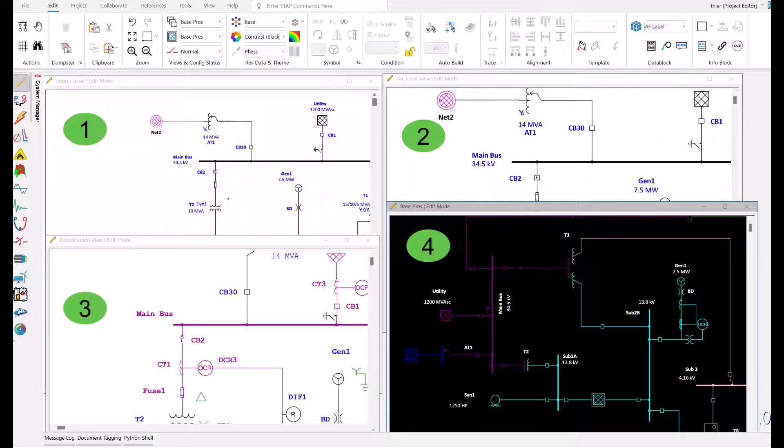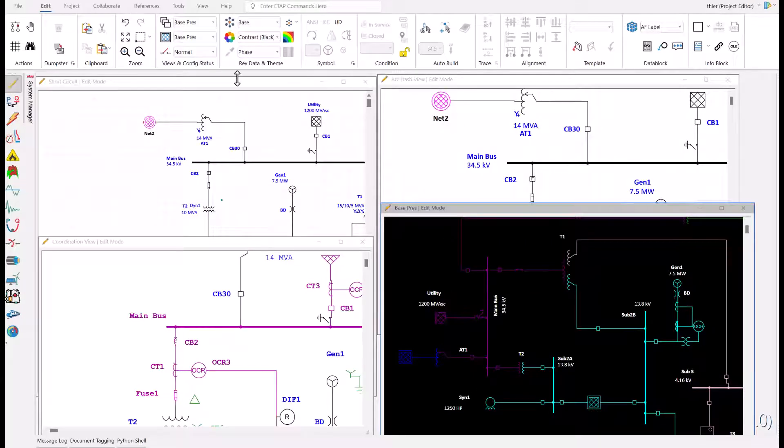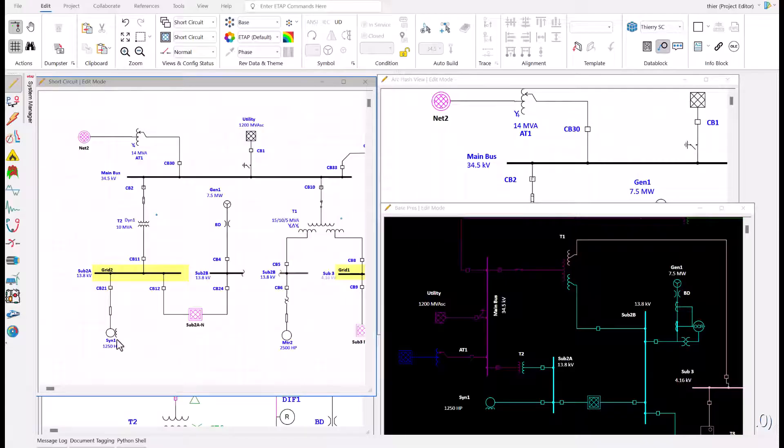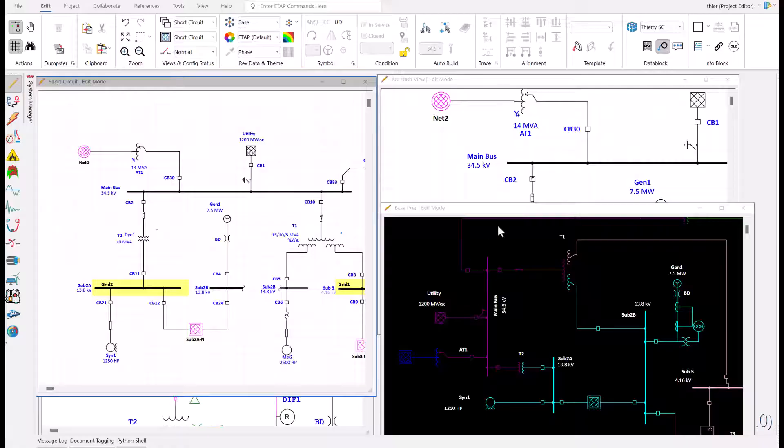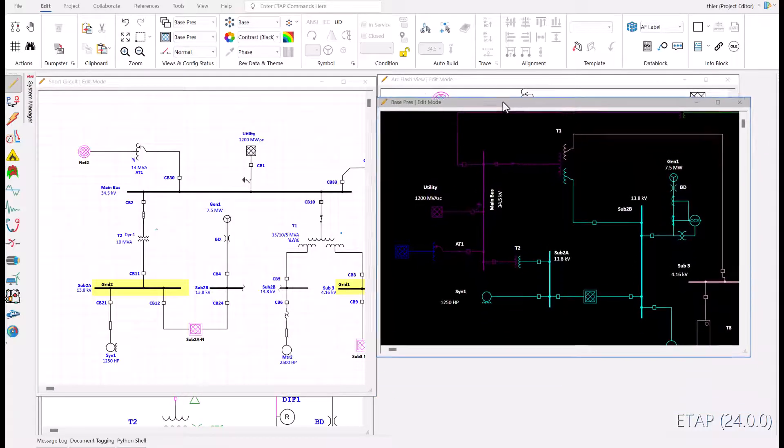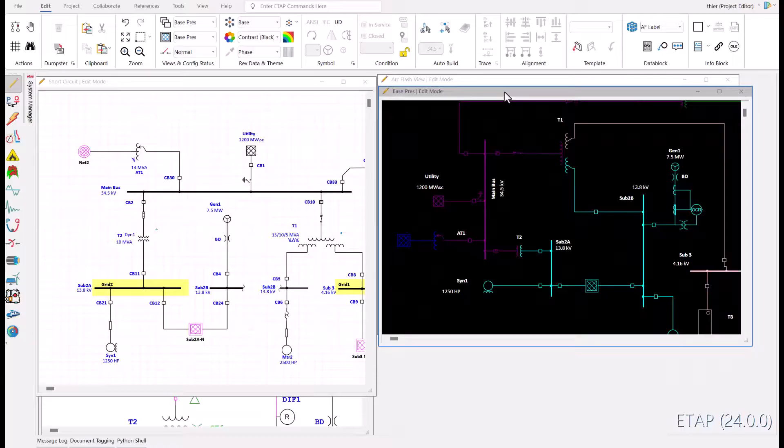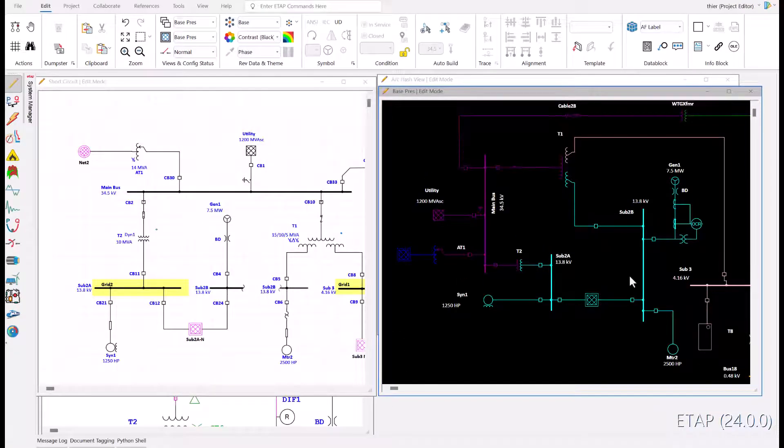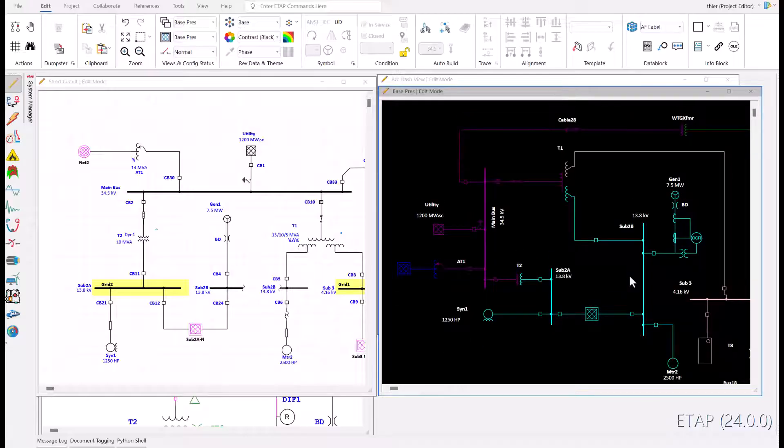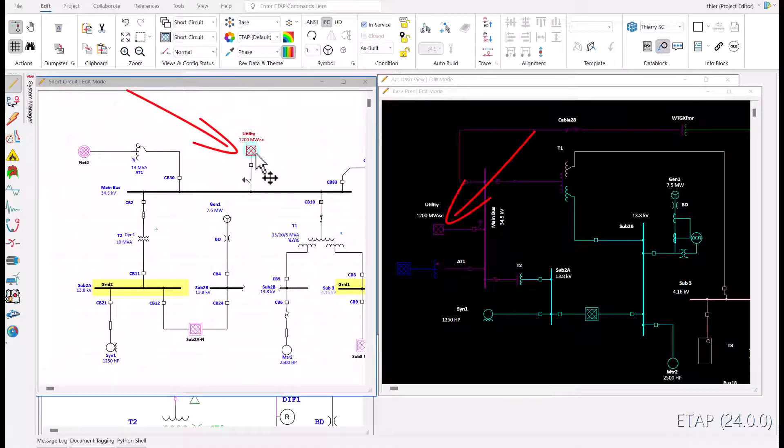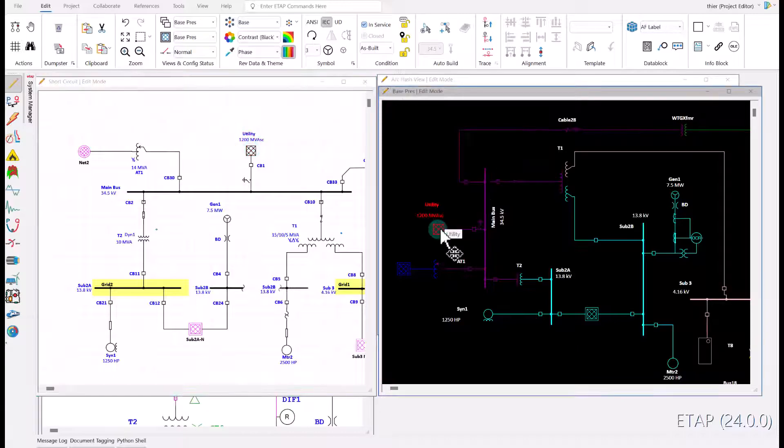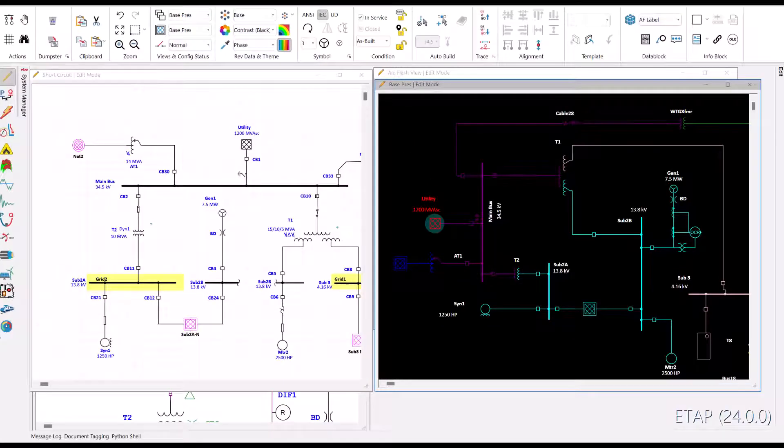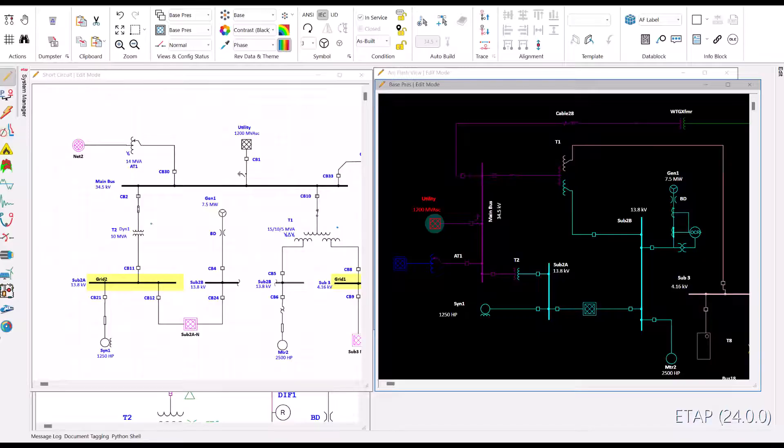Window 1, top left, short circuit window. Notice that all the components are identical between the short circuit window and the original one line. However, the view is different. For example, the utility in the short circuit presentation is on top of the bus. However, in the base case presentation, the same component is on the left side of the bus. The base case presentation reflects the identical layout from the facility's as-built one line drawings. But since we will be discussing short circuits, I want to make the drawing top down so that it is easy for the audience to follow.